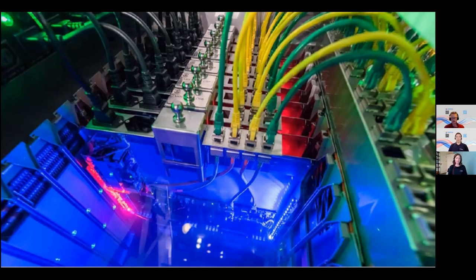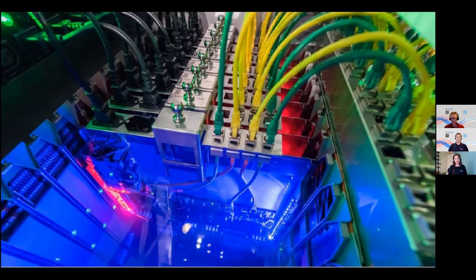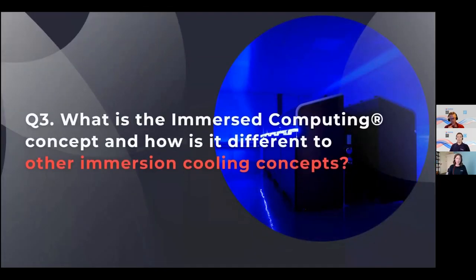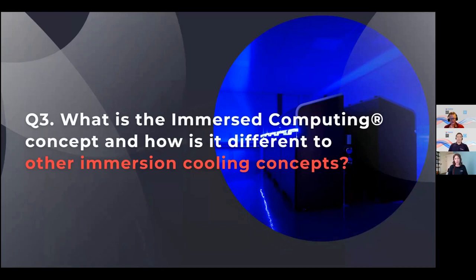At Asperitas, we use full immersion natural convection cooling, which means 97% of the heat is captured to the water, only 3% going to the air side, minimizing the chiller power requirements. And because it's natural convection, there's no energy penalty to achieve this. So more of the energy available is utilized by the IT equipment for its production workload. And the IT is cooled well enough for it to do its work effectively. So efficiency is key.